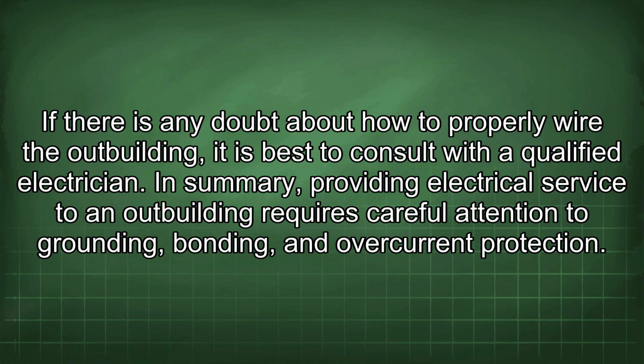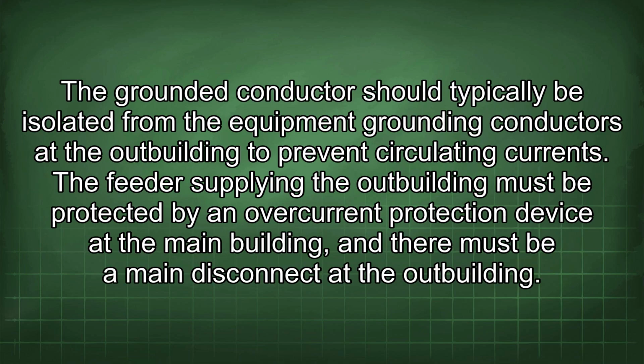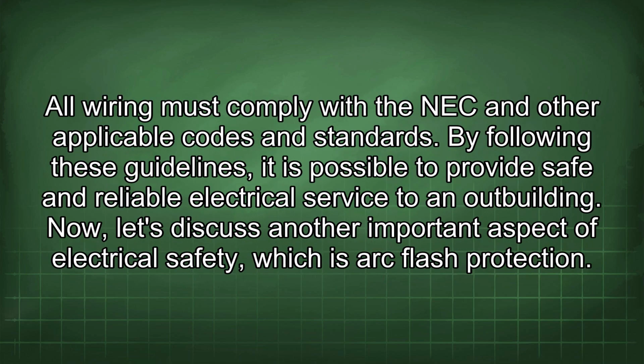In summary, providing electrical service to an outbuilding requires careful attention to grounding, bonding, and overcurrent protection. The grounded conductor should typically be isolated from the equipment grounding conductors at the outbuilding to prevent circulating currents. The feeder supplying the outbuilding must be protected by an overcurrent protection device at the main building, and there must be a main disconnect at the outbuilding. All wiring must comply with the NEC and other applicable codes and standards. By following these guidelines, it is possible to provide safe and reliable electrical service to an outbuilding.